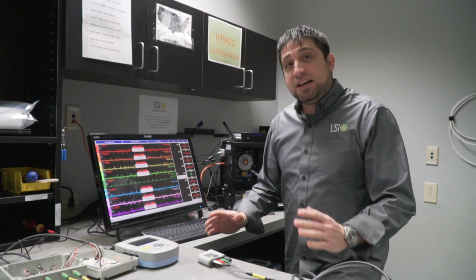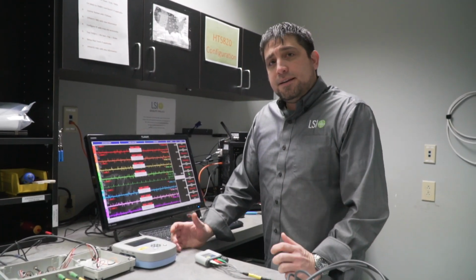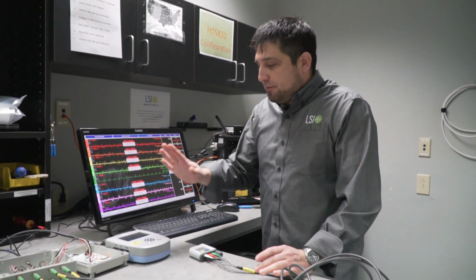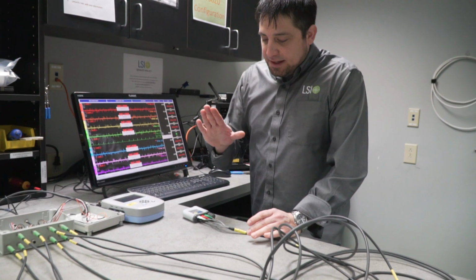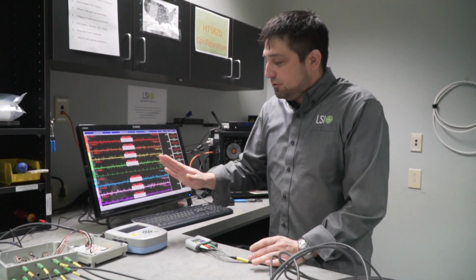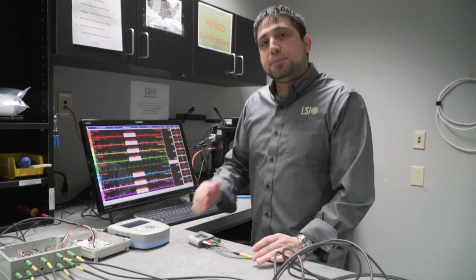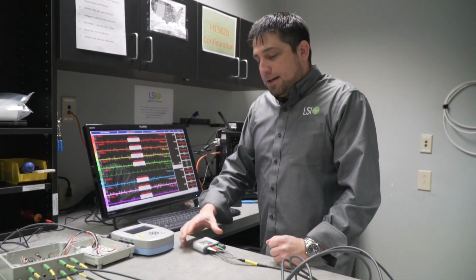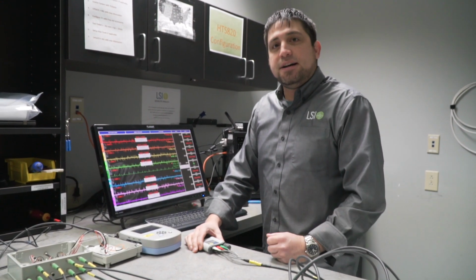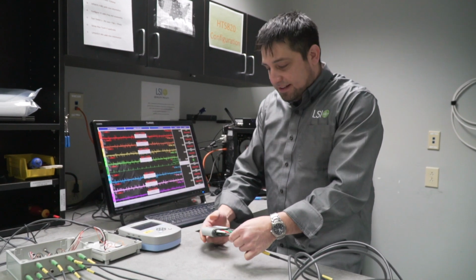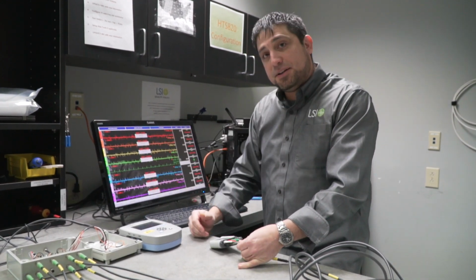Just a recap of the overall project. The original problem was we were having to use one simulator and test one transmitter at the same time. So the goal was to be able to use one simulator and test multiple transmitters. That was the original scope of the project. In doing our design, we have a transmitter that transmits information. And typically this would be hooked up directly to the simulator.